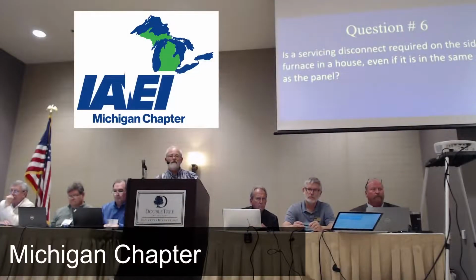The mechanical code, was that in commercial for having to have a disconnect within 6 feet, or was that for residential also? When you get to a more stringent code, that's the one that applies. So that's why I say get on board, if you're an inspector, with your mechanical team, and if you're a contractor, search that out at the rough so that when you get to the final, you're in the right spot. The mechanical code requires that the mechanical contractor assure that there's a disconnect on or immediately adjacent to, which is a 6-foot rule or within sight. It says on or immediately adjacent to in both codes.